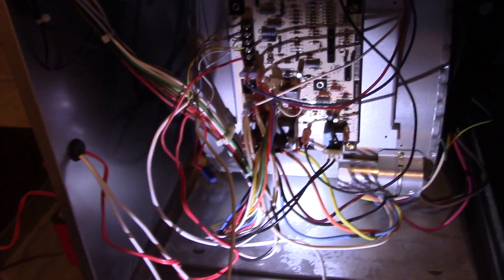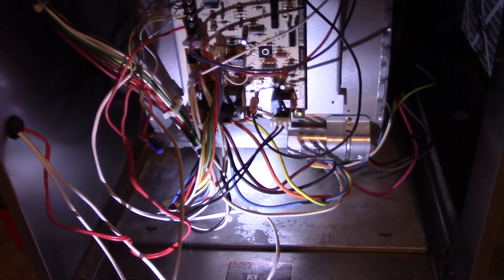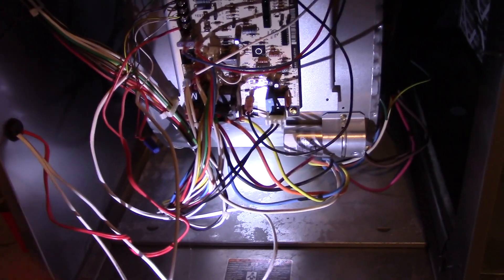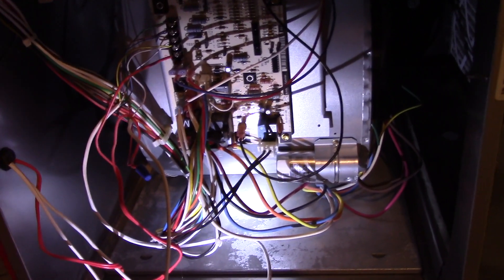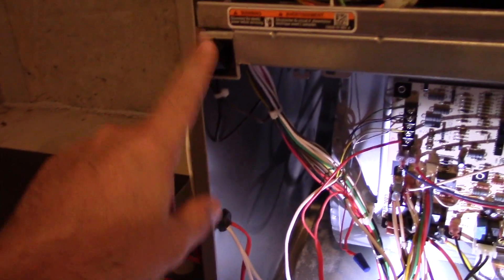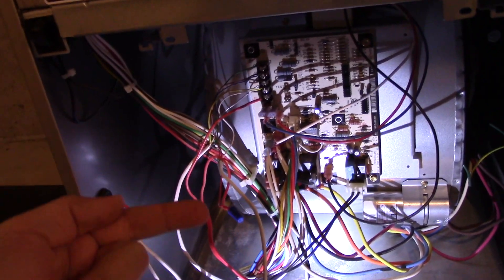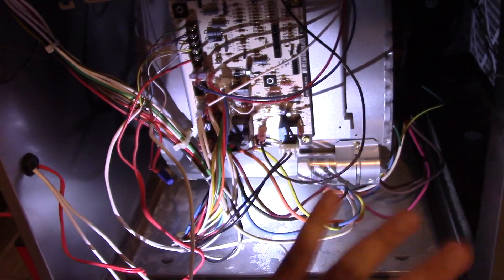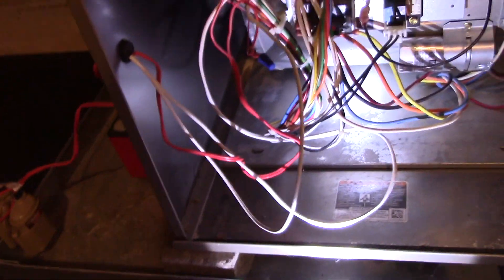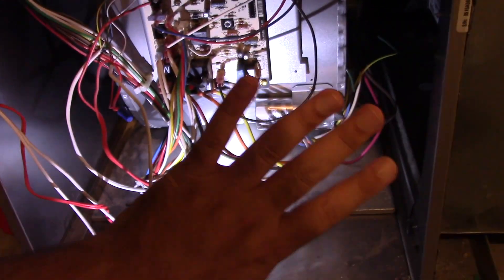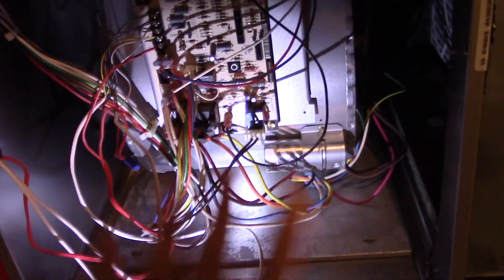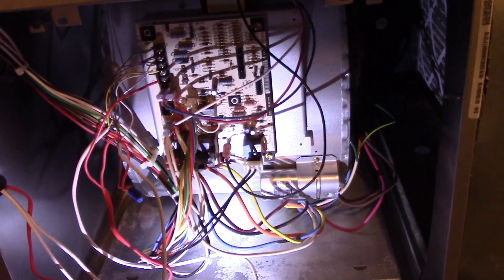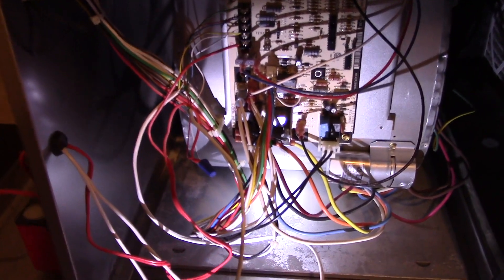If you're not sure of the wires, let me show you an example of how you can do it by audio. You're basically going to very carefully listen to how the blower sounds when it turns on. Now, obviously, you're going to be doing this with power applied, so I want to have a couple of disclaimers here for safety. First things first, when you push in this switch, the board's going to energize and the blower's going to come on. Please, common sense, don't put your hands anywhere inside here while this thing is going. And second of all, if you have anything loose on the floor that's lightweight, like loose pieces of paper, some bags or stuff like that, move them out all from this area. That's a very powerful blower that can pull in a ton of air. You don't want that stuff getting pulled in and possibly going on the blower.